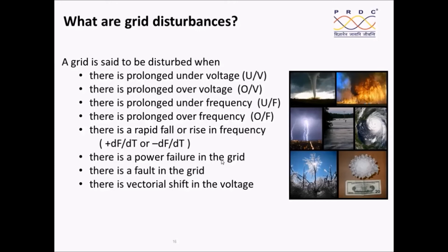Within no time, that vectorial shift in the voltage is sensed. Using that also, it is possible to find out that there is some problem in the grid. Based upon that, we can try to ensure that islanding happens. Therefore, these are the various measures by which grid islanding can happen.